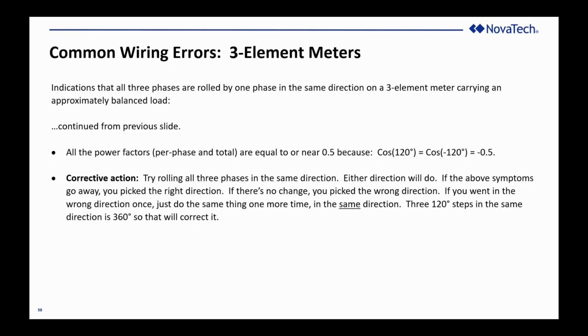Corrective action. This is cool. I like this. So it occurred to me when I was thinking this through, you have to roll all three phases to correct it. So which direction do you go? Well, you really can't tell from the meter which direction is right, which direction is wrong. So what I'm suggesting is roll all three phases in either direction. If there's no change, you picked the wrong direction because you'll now have a meter where everything was rotated one phase in the opposite direction, and all of the symptoms will be exactly the same. But if you rotated it in the right direction, everything will go back to normal.